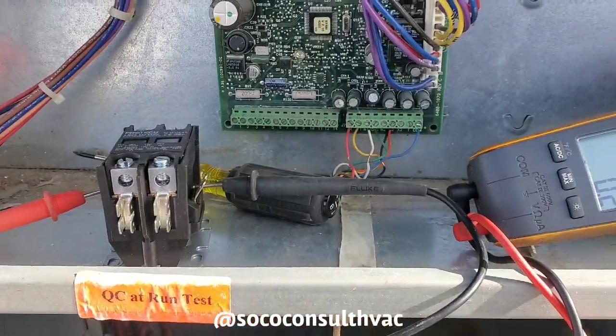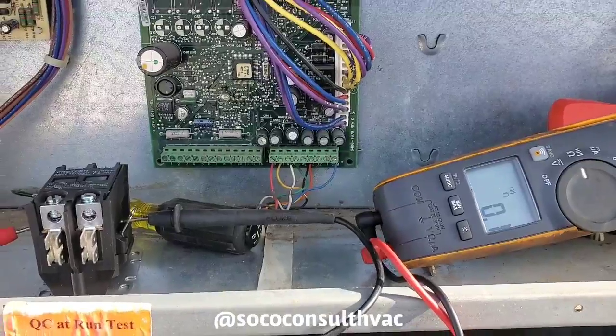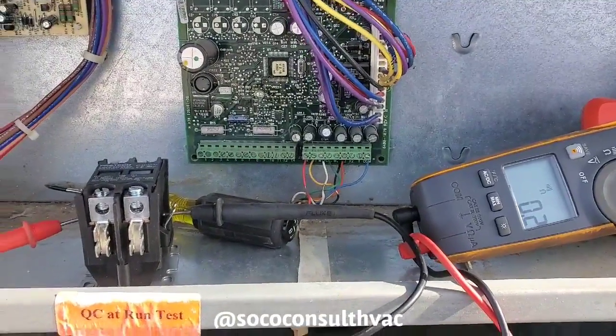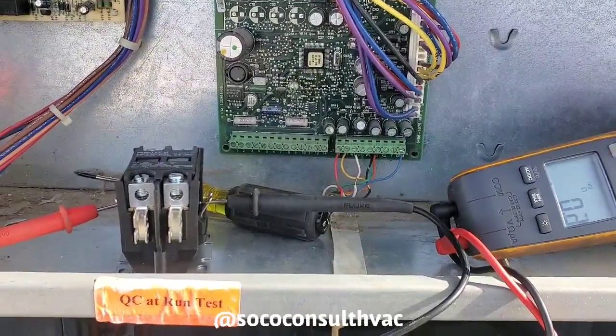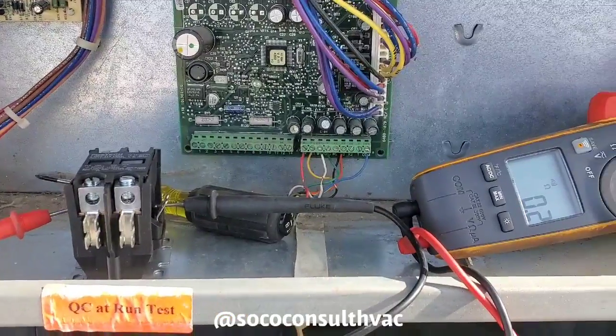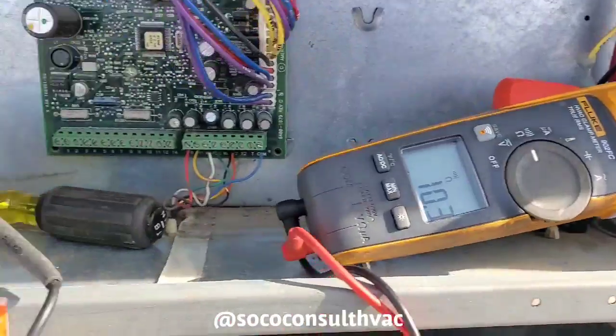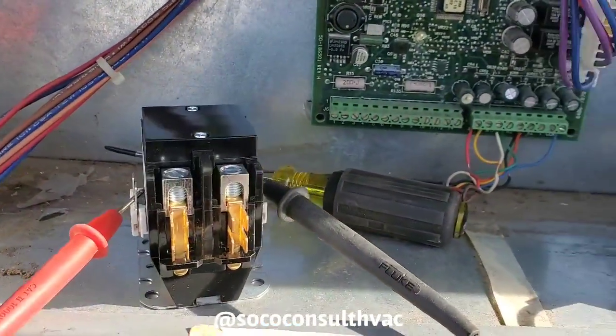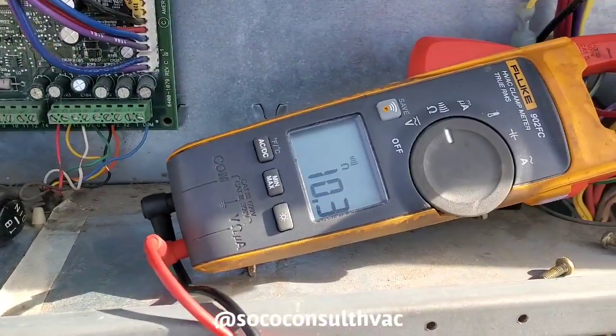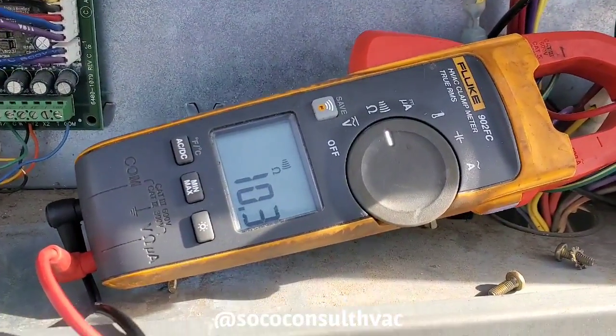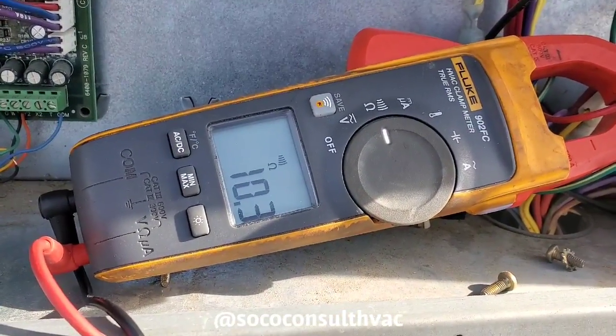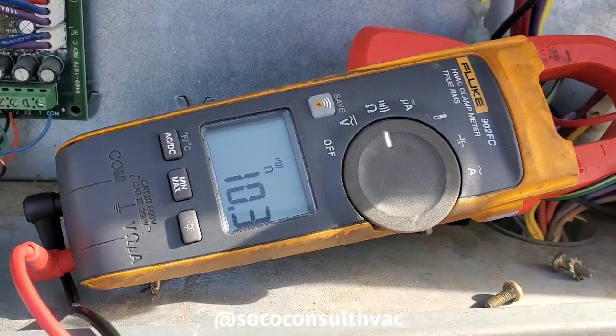So we're going to replace this contactor, but before we do, just for kicks and giggles, I want to ohm out what a contactor coil typically should ohm out as, so I can use that as a reference next time. All right, so we're ohming out our new contactor coil just so I can kind of put in the back of my mind what I would expect to see ohming out a coil. And as you can see, we're ohming out right at 10 ohms.